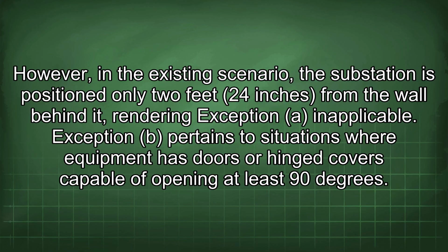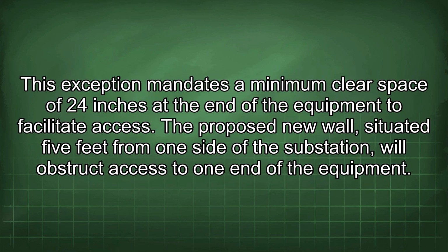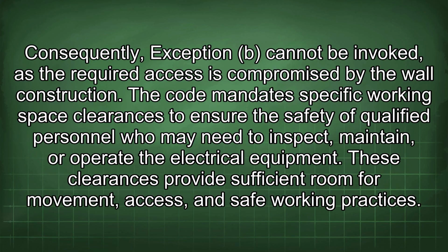Exception A inapplicable. Exception B pertains to situations where equipment has doors or hinged covers capable of opening at least 90 degrees. This exception mandates a minimum clear space of 24 inches at the end of the equipment to facilitate access. The proposed new wall, situated 5 feet from one side of the substation, will obstruct access to one end of the equipment. Consequently, Exception B cannot be invoked as the required access is compromised by the wall construction. The code mandates specific working space clearances to ensure the safety of qualified personnel who may need to inspect, maintain, or operate the electrical equipment. These clearances provide sufficient room for movement, access, and safe working practices.